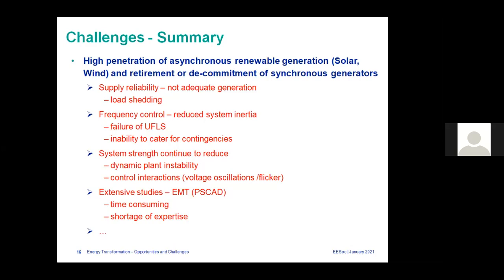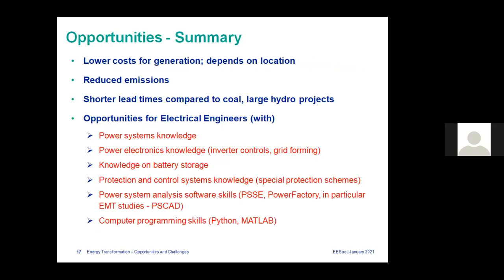Then, as we mentioned, frequency control is the issue, especially because of the system inertia reduction. And this is a major issue because there can be failure of under frequency load shedding. If you don't have enough inertia, frequency can drop. If there is an incident, frequency can drop significantly faster compared to if you have high inertia. Then normally in the system, you have under frequency load shedding to capture unexpected faults. If you can't sustain the frequency, or if there is not enough generation to match the demand, you have a number of loads selected to shed or trip. But those relays need some time, about a few hundred milliseconds, to do that shedding process. But if the frequency drops much quicker, under frequency load shedding will fail. So frequency will continue to drop, and you will have a cascade failure, and you might have a blackout.